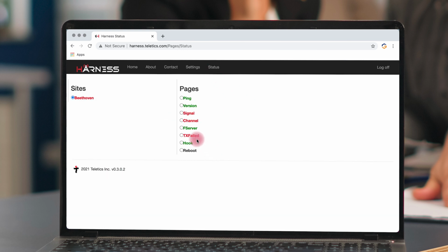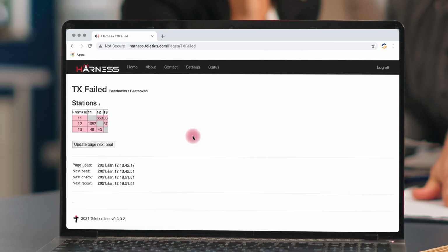Also, there's a diagnostic on the radio side that allows you to essentially ask the network the question, who is the one radio that nobody can talk to and that nobody can hear. And if that diagnostic doesn't pass, then there's an issue that either a station is too far away or something has been put in between that station and the rest of the network.